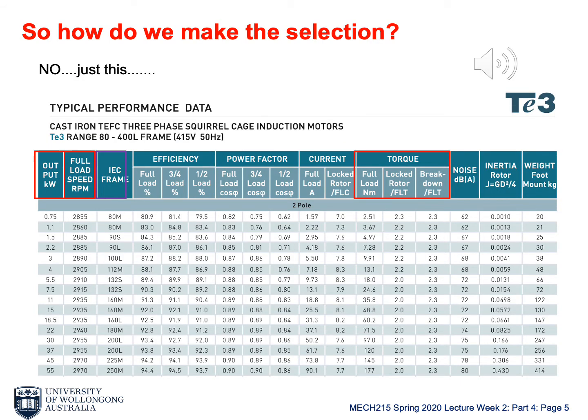Some other motor catalogs may not sort the motors by output power. They might sort by RPM. In this case, this table shows mostly all the 3000 RPM motors. You can look at the second column. They are all very close to 3000 RPM, with only a slightly different slip. But the output power goes from 0.75 up to 55.